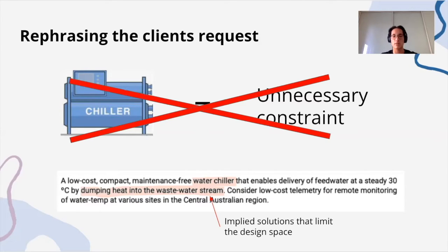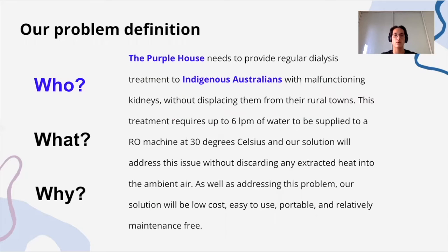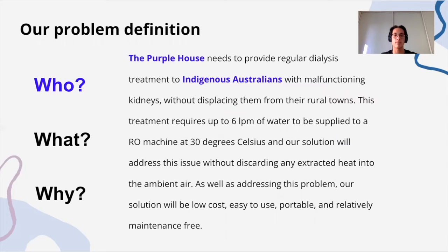Rather, they desire that extracted heat not be dumped into the ambient air, meaning heat doesn't necessarily have to be dumped into the wastewater stream. By clarifying the customer's requirements, our problem statement doesn't include these two unnecessary restrictions that would have otherwise limited the range of ideas we explored in the conceptual design phase. Our statement uses the who, what, why structure outlined by Michael Schofield, and we identify the Purple House and Indigenous Australians as being those who are dealing with the problem. We conveyed what this problem is: regular dialysis treatment must be provided without displacing Indigenous Australians from their rural towns, and that this treatment requires up to 6 litres per minute of water supplied to an RO machine at 30 degrees Celsius, without extracted heat being discarded into the ambient air. As a group, we identified that processing up to 6 litres per minute of water and not dumping heat into the air were imperative constraints.